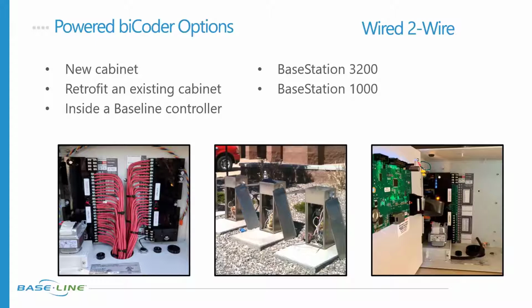The last one on the far right is a power decoder inside a Baseline controller. This looks like my 1000 controller here in my office with a power decoder in it. We've always had this option, right? You could buy a Base Station 1000 or a Base Station 3200 with a powered decoder in it, and that's how you'd bring two-wire technology to your conventional wire site, because all of our controllers are two-wire controllers. This is how we interface with that conventional wire without having to replace the wire.